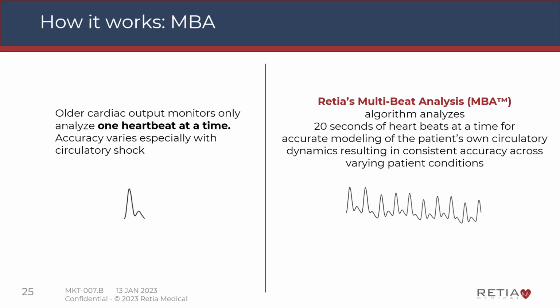How is this done? Retia's MBA algorithm, or multi-beat analysis algorithm, analyzes multiple heartbeats from the blood pressure signal to accurately model the patient's circulation. This provides the ability to accurately track changes in vasomotor tone as measured by the SVR parameter. Further, analysis over multiple heartbeats allows for consistent accuracy even when consecutive heartbeats are irregular, as happens during arrhythmias.